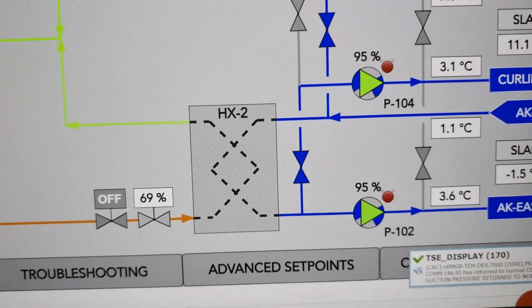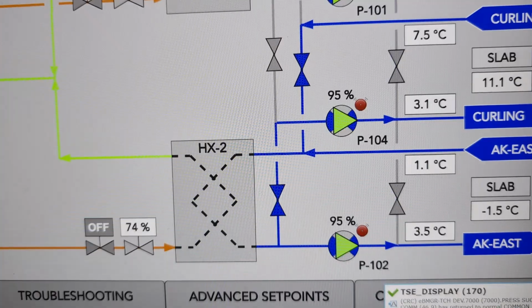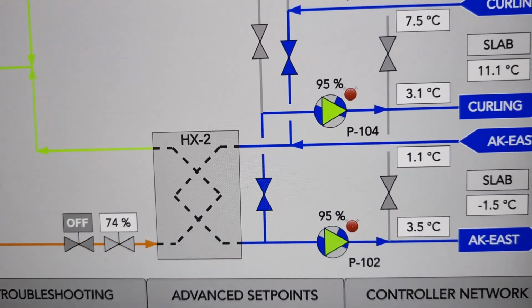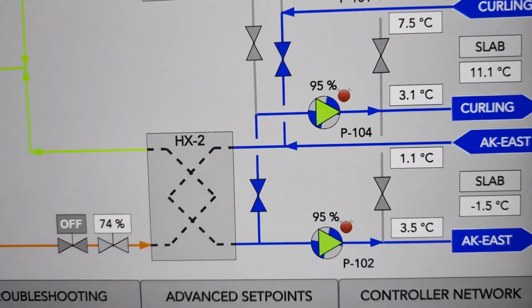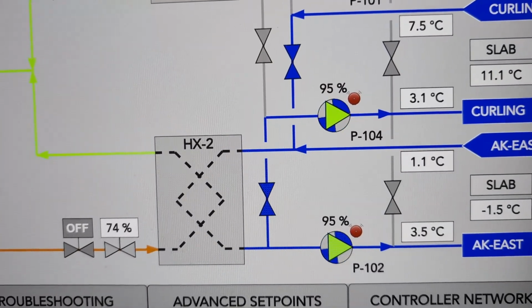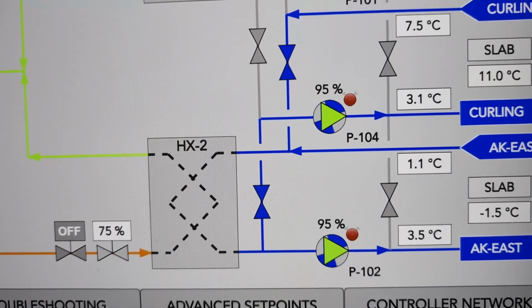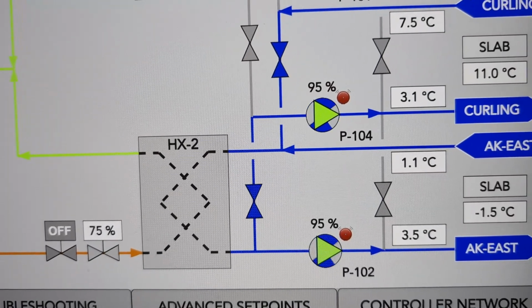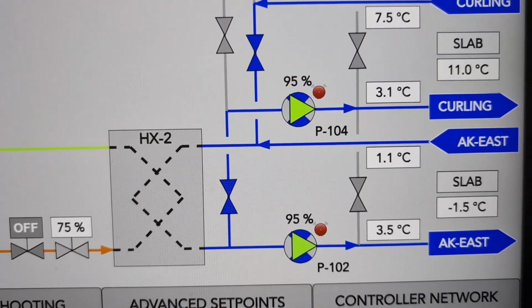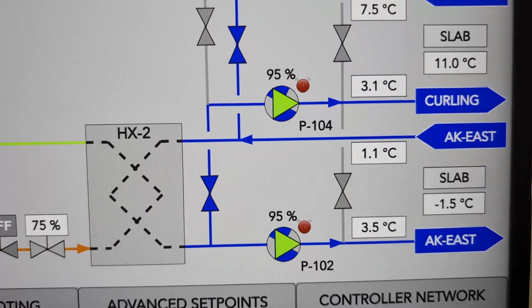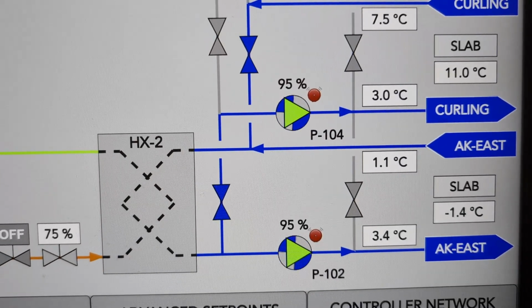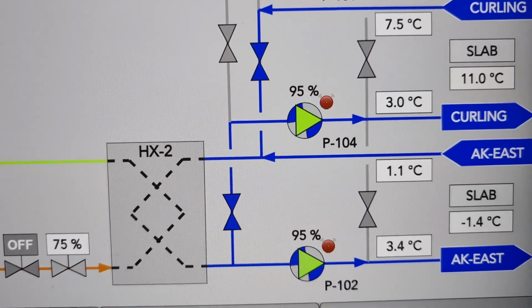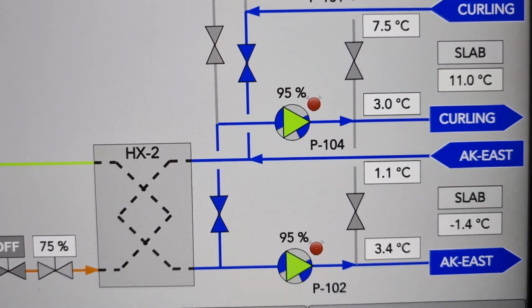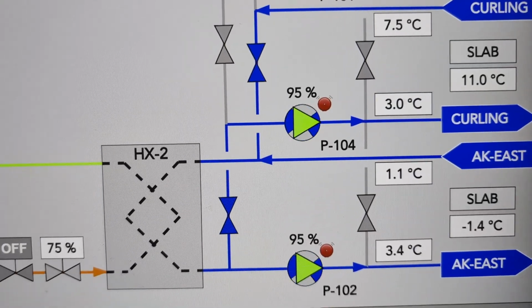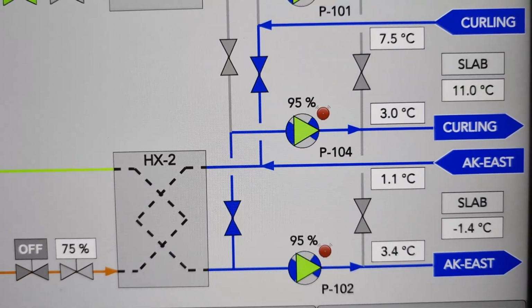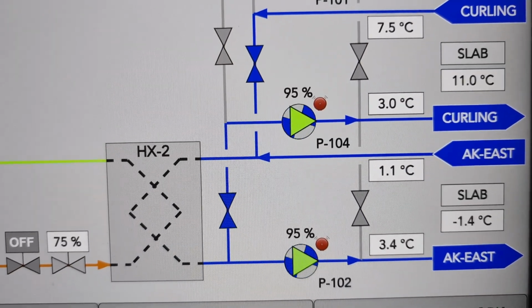So it's not even been half an hour, and you can see the brine's, I'd say, fully mixed at this point, and what you're seeing on those temperatures there, it's going out at 3 and coming back at 1. That's just the heat that it's giving up as it warms up the AK slab, and then it's going out to the curling at 3 and it's coming back at 7. You can see the slab temperature saying 11, so there's still lots of heat that it can transfer there to keep warming up that AK slab.